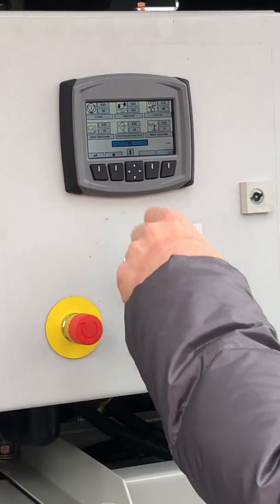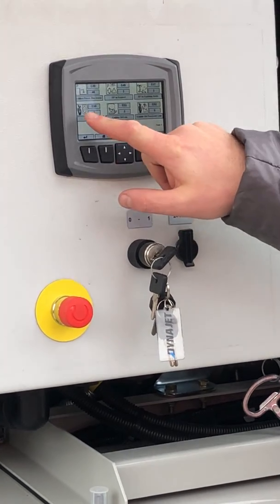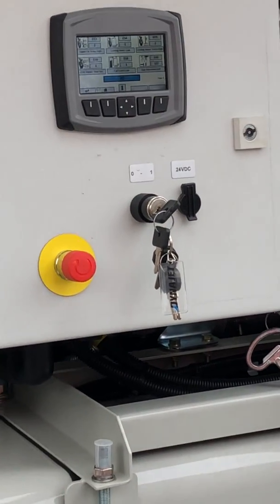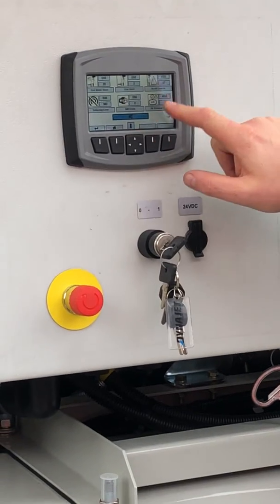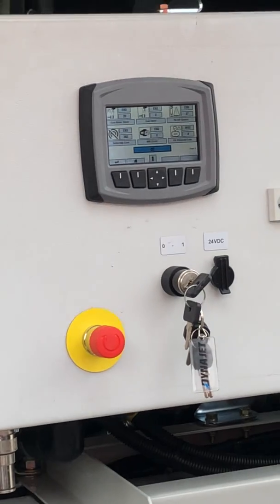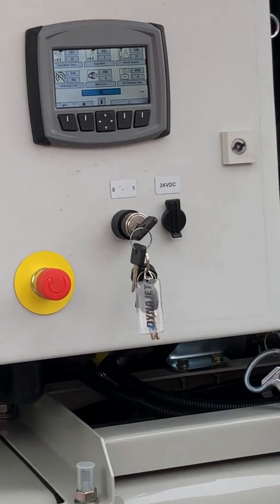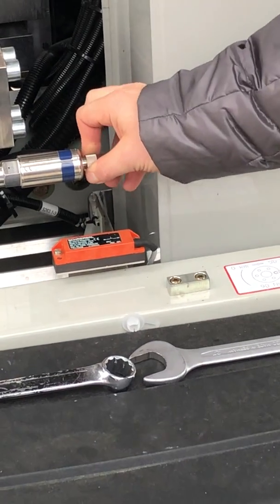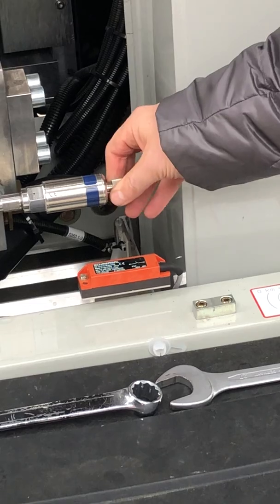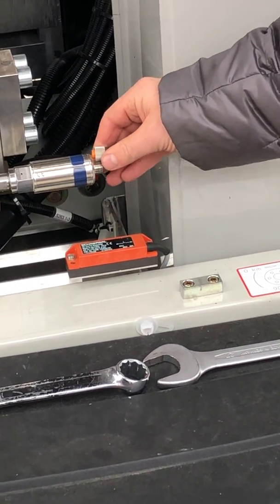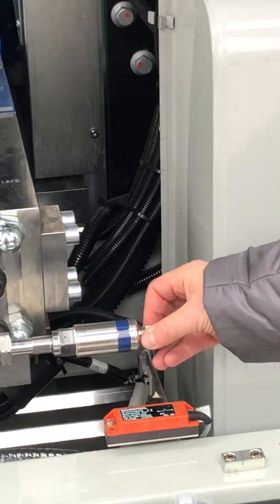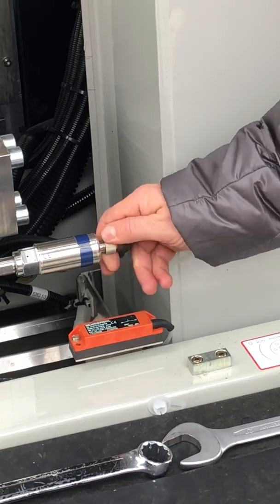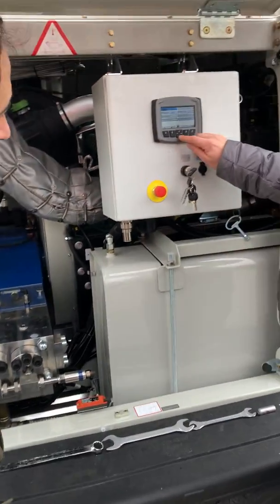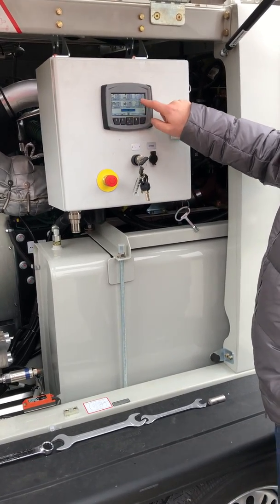We also have a fault history. Here we have all the faults that the machine can produce, with the long text and how often during the life of the machine they have happened. Let's take, for example, and this is the one that I'm always using to show how the machine works, E80, the HP sensor, a high pressure sensor. This happens 17 times in the life of the machine. I take the sensor off. The machine will go into a red error right away, and it would stop if it were running. We go into the fault history and we see that this is at 18.